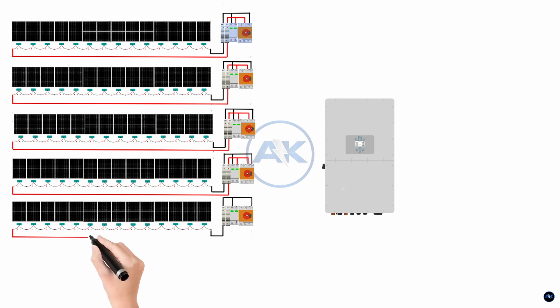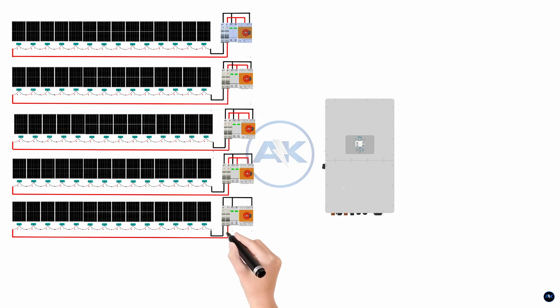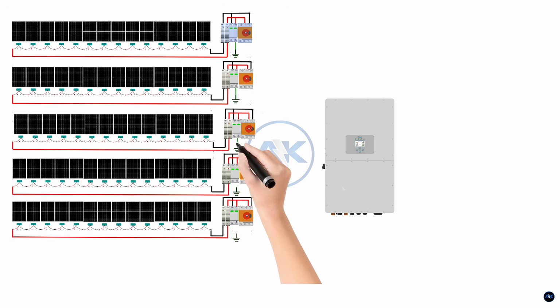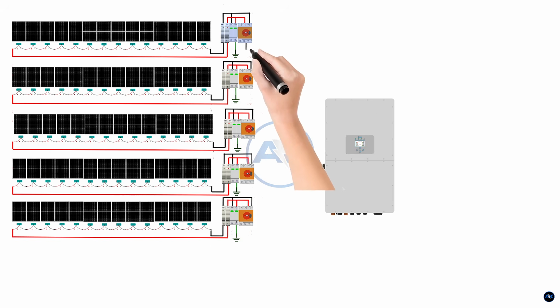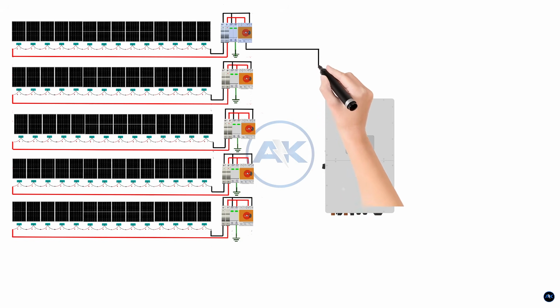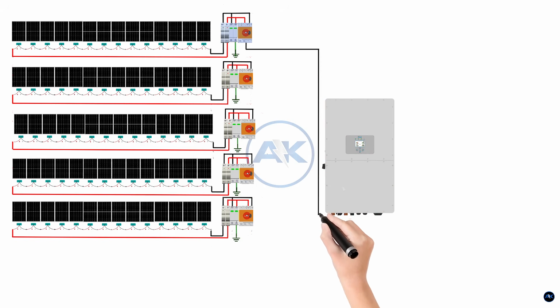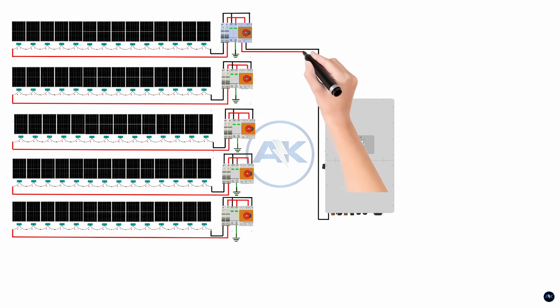Now we connect the strings to the DC combiner box. Bring the positive and negative cables of each string into the combiner box using proper DC solar cable and glands. Keep each string separated and clearly labeled. For each string, connect the positive cable first to its own DC fuse. We use a 20-amp GPV DC fuse rated for 1000 volts. This fuse protects the string and prevents reverse current from other strings.